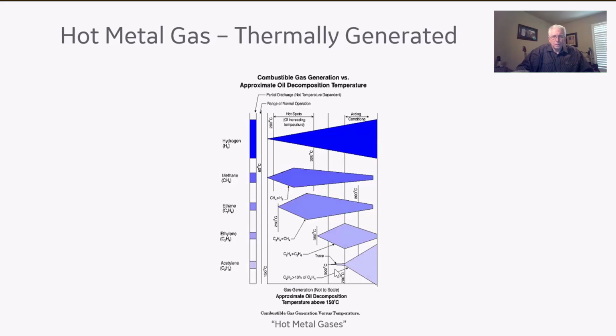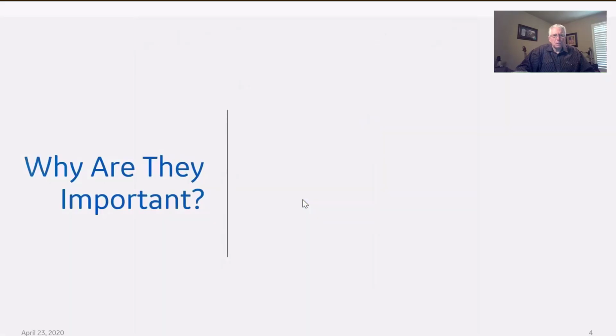Not necessarily. We did talk about this when we looked at load tap changers, for example: when you flash oil and pull a dissolved gas sample, and you look at the relationship of these hot metal gases, you can see plainly an arcing signature, how that forms, what it looks like, how consistent it is. For those that may not have made that call, we may visit about that for a moment as well, but not too much time on that. So when I look at this, I generally think in terms of just a progression, right?